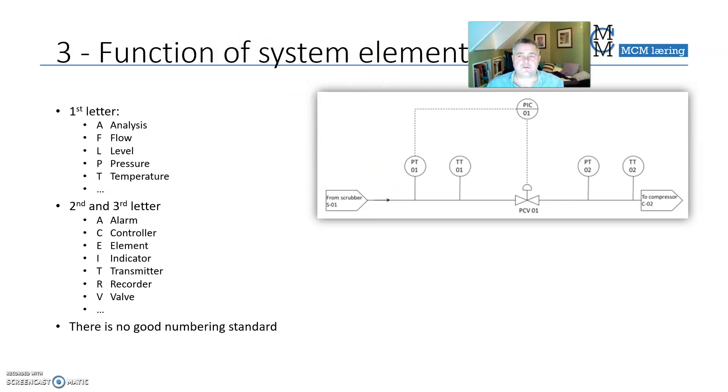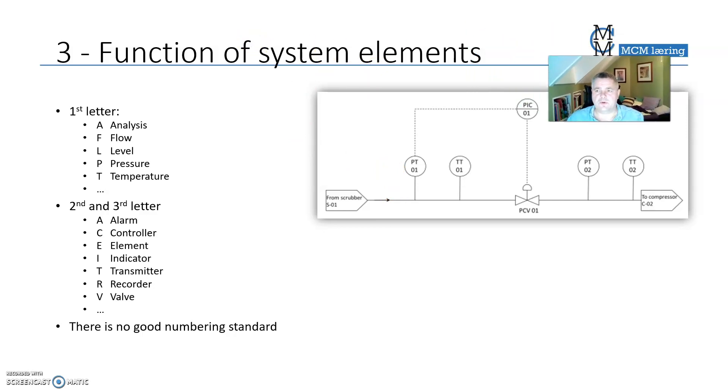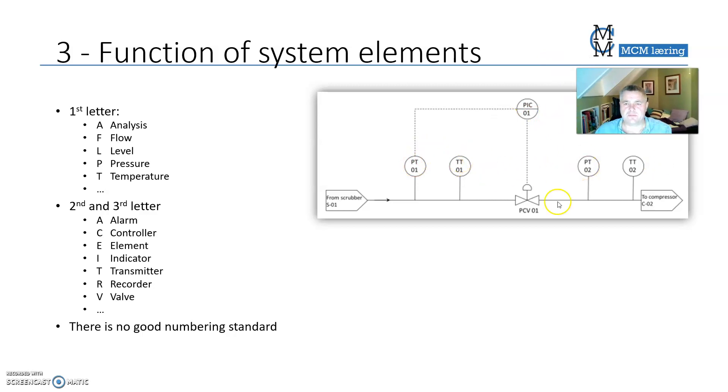The function of system elements is shown with the letters inside. The first letter describes what it's for: is it for analysis, flow, level, pressure, temperature, or whatever. This is for pressure, this is for temperature. The second and third letter is what it does. This is a pressure transmitter, so this is a pressure sensor. This is a temperature transmitter, temperature sensor.